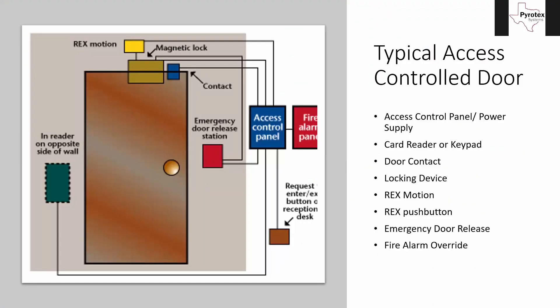Here is a diagram of a typical door setup, whether it's the only access control door in the building or one of many in a school. You have an access control panel — the brains of the operation and your power supply. I want to stress: we never use the fire alarm system to power a door lock. Door locks are not UL listed as fire alarm devices, so they don't get powered by our system.